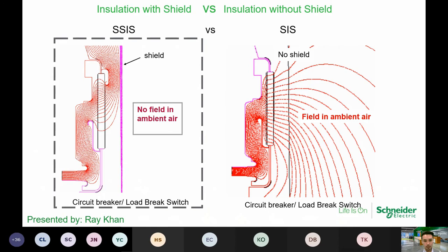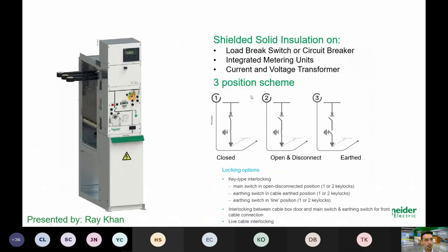Over here it shows some of the basic features. For instance, the SSIS, the PremSet, is using the three position scheme. Here you can see it's a closed position, and in position two we have the breaker opened and the line connector still intact. In position three, you can see the breaker is open and the earthing switch has been closed as well. This gives a summary of what a three position scheme means.